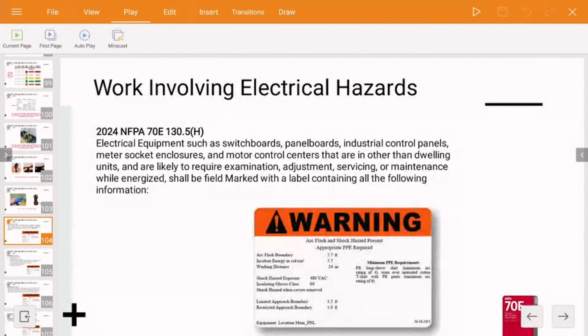Make it big enough. So if you look here, this is an example of a label that you should see on every piece of equipment out there in the field. In fact, the 70E says the owner of the equipment is required to put a label like this on every piece of equipment. They have to maintain it, and they have to maintain the backup documentation that the engineer gave them for their study.